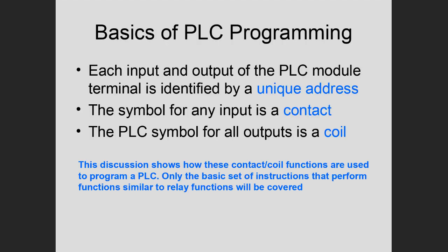So you know by now that each input and output in the PLC, you connect to a screw terminal on the input or output module. Each screw terminal has an address, and you can map a bit position in the input or output image table, that is the data table, to a screw terminal using an address. You guys have done that. You drag instructions to your rung, and you gave it an address, and each one of those addresses points directly to a cell in the input or output image table. So that should be familiar to you.